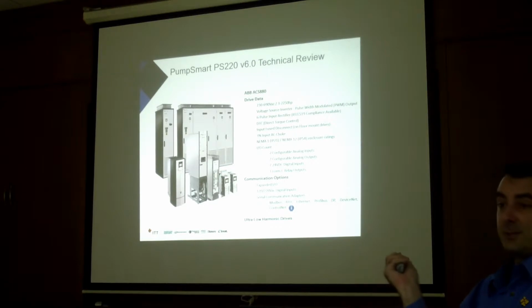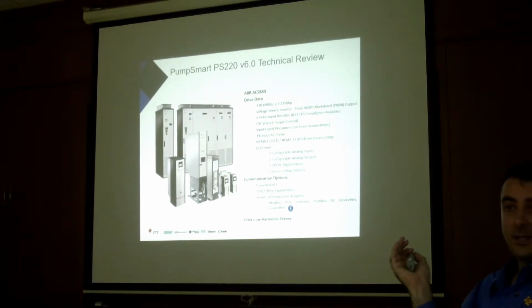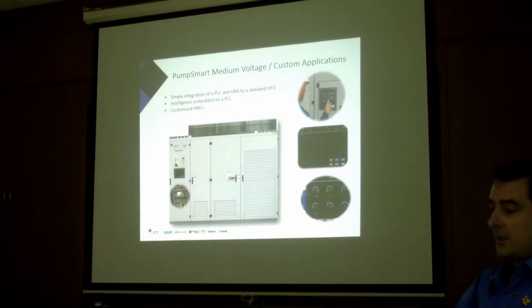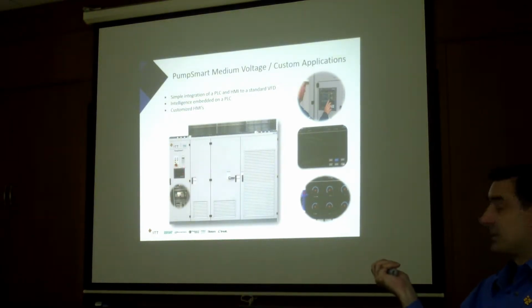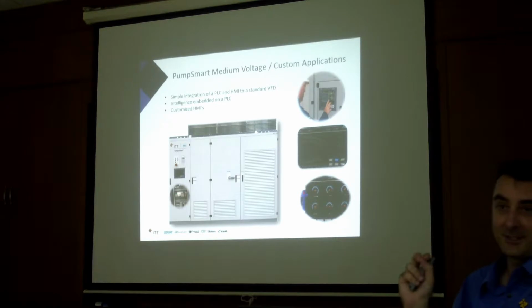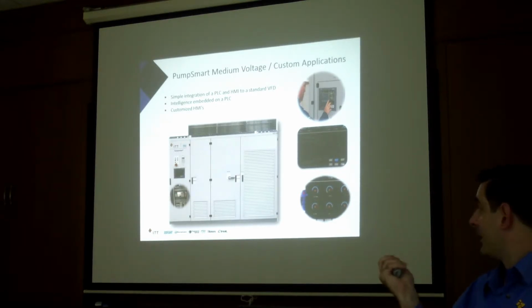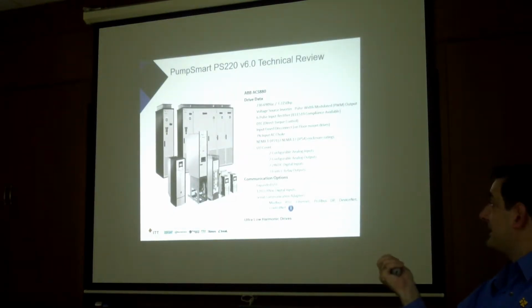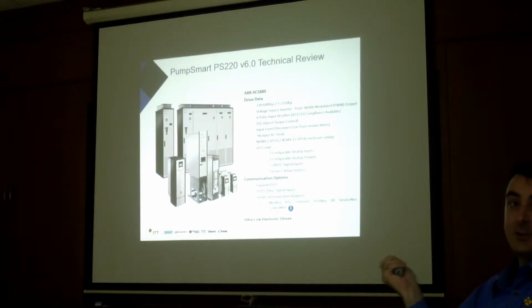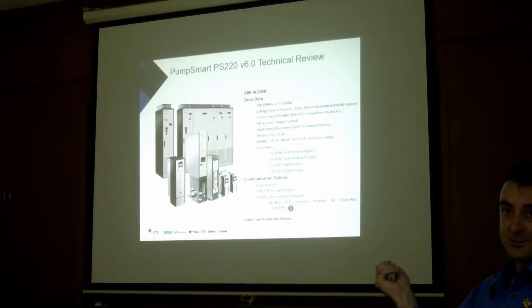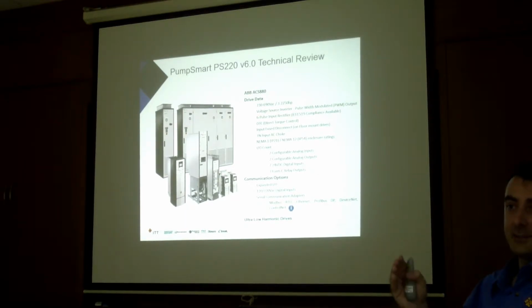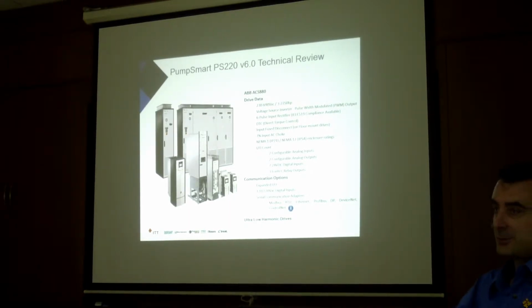It's just some details on the hardware. So it's standard ABB hardware. Any option the customer wants, we can include. The medium voltage is customized. I need to make this clear. This is not very clear to someone, even internal. The PS220 low voltage is only available on ABB ACS 880 at the moment. We are looking at another brand, but it won't have all the same features. This will always be the best product in the low voltage because the torque is very accurate. No other brand can do it accurately, so we can't do the same control.